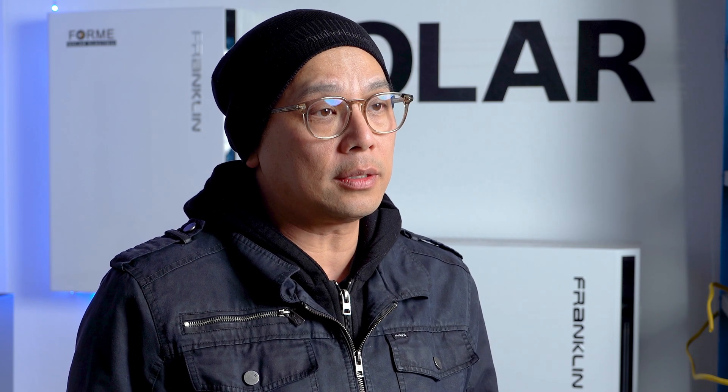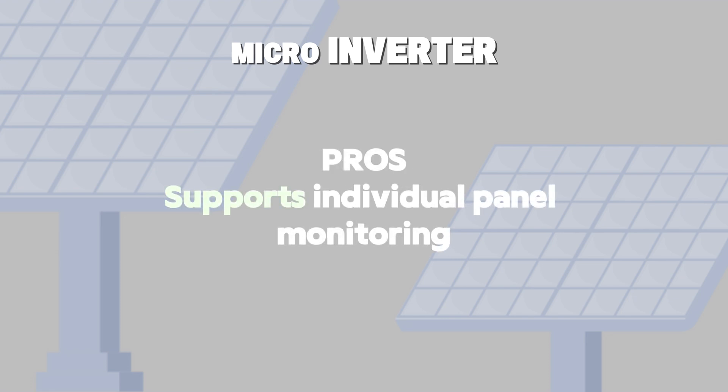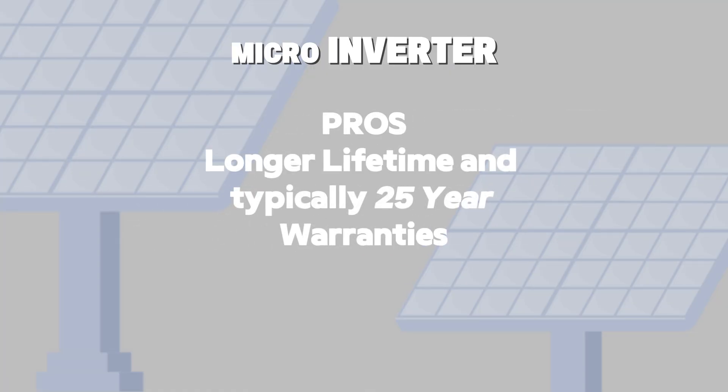Microinverter systems fix these issues by allowing each panel to adjust according to its own conditions. So for example, shading on one panel won't necessarily affect the rest of the panels in that string, instead allowing each of them to adjust individually rather than being dragged down by the one panel that's underperforming. You also have the benefit of seeing the real-time performance of each individual panel. Microinverters, which have a longer lifetime, typically come standard with those 25-year warranties instead.